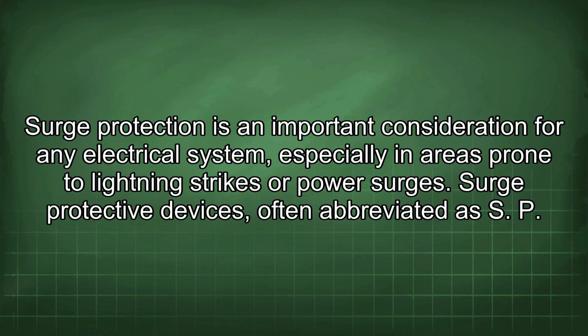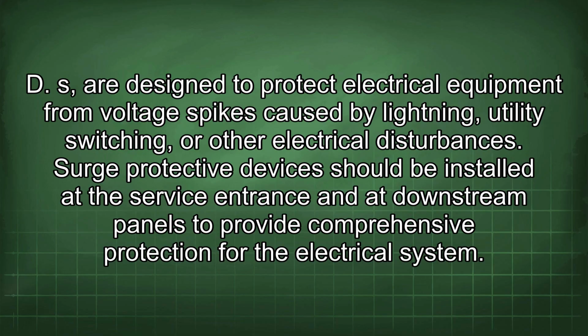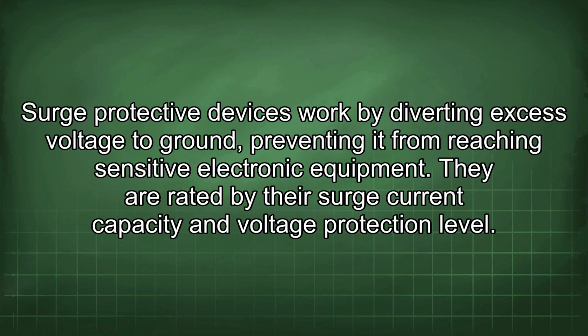Surge protection is an important consideration for any electrical system, especially in areas prone to lightning strikes or power surges. Surge protective devices, often abbreviated as SPDs, are designed to protect electrical equipment from voltage spikes caused by lightning, utility switching, or other electrical disturbances. Surge protective devices should be installed at the service entrance and the downstream panels to provide comprehensive protection for the electrical system. Surge protective devices work by diverting excess voltage to ground, preventing it from reaching sensitive electronic equipment.